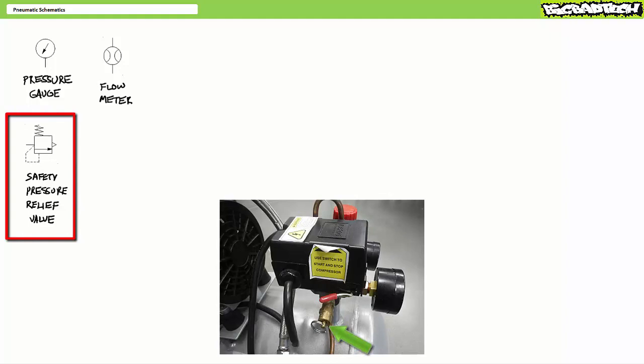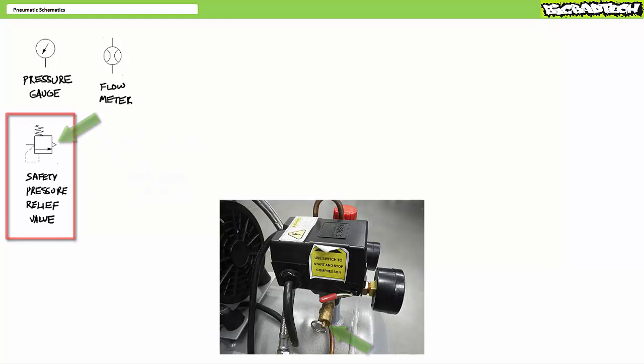Safety pressure relief valves are normally closed valves that sense pressure on their input. If, however, pressure inside the receiver rises above the set value of the safety pressure relief valve, the safety pressure relief valve opens and vents the excess pressure from the receiver to the atmosphere. Note the exhaust port back to atmosphere.